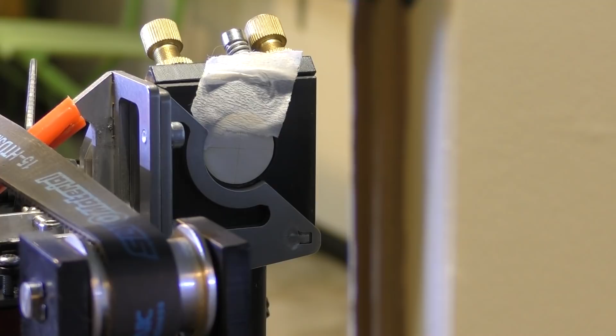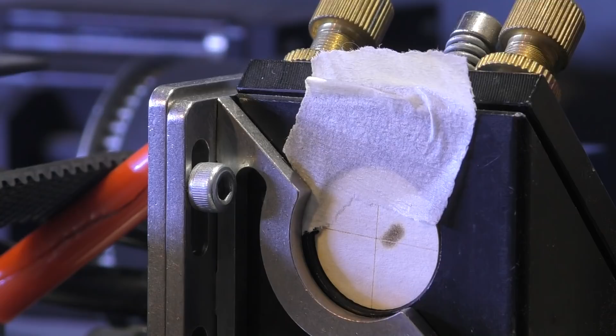Now it looks quite a long way out, doesn't it? Should I worry? Well, the answer is, in this case, no, I shouldn't worry. It's about the correct height, but it's out in X. It's probably out by more than 2 millimetres, it's probably 3 millimetres off centre. But let's not worry about that because I've got a secret weapon on this machine. So that was our target burn. Let's see how close we are with the next burn. Not far off. We're slightly high and slightly too far this way.